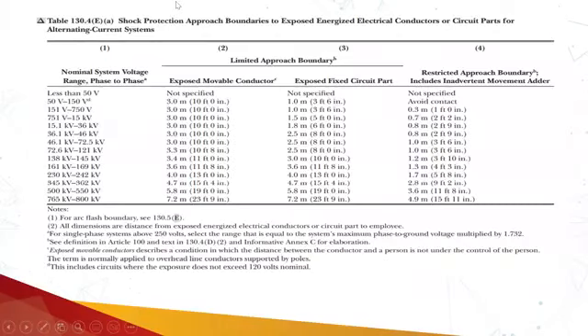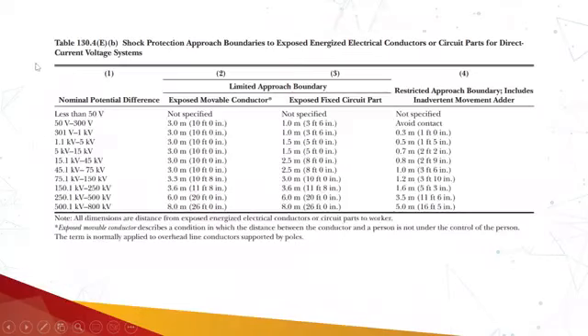How will we calculate these two boundaries? The voltage levels will be given to us. For the AC voltage level, if it is a movable conductor, we will use column number 2. If it is a fixed conductor, we will use column number 3. For both, the restricted approach boundary will be the same. In the exam, we have to make sure whether it is talking about alternating current or direct current. If it is DC, then we will use Table 130.4(E)(b).